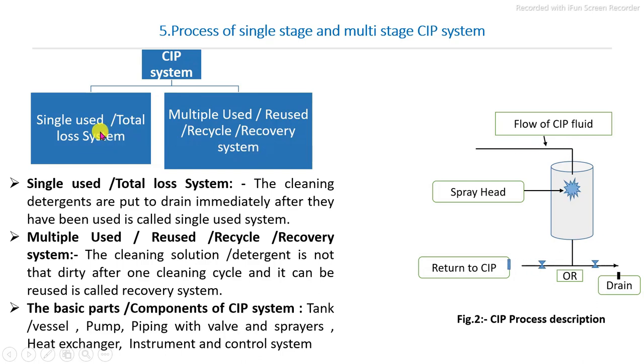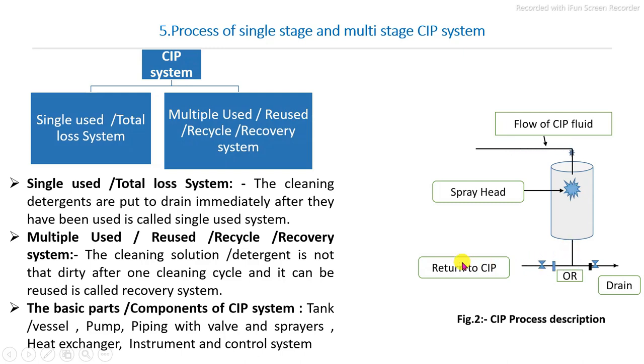The basic difference between them is that in the single-use system, whatever detergents are used one time are not recycled or reused — the detergent solution is directly drained out after use. This is called the single-use total loss system. In the multiple-use system, whatever detergents are sprayed or flow through the processing line are recycled and stored in the detergent storage tank, and then reused for the next batch cleaning process.